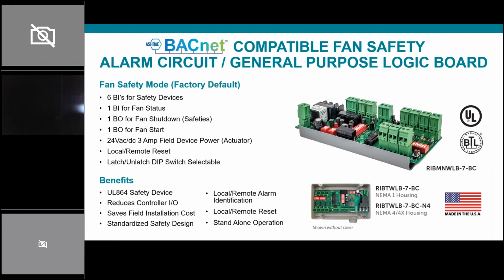So at the board's factory default setting, the MNWLB is in fan safety mode. The board has 7 binary inputs and 2 binary outputs. 6 of the binary inputs are for safety devices such as your smoke detector, static pressure, or low limit freeze protection sensors. And these 6 inputs are tied to binary output 1 for fan shutdown. Now, these 6 inputs can be configured to be either normally open or normally closed. However, by default, the fan safety function requires normally closed sensors.